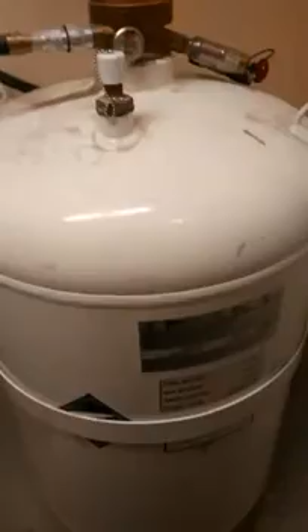FM200 fire suppression system is a clean, non-electric conducting, and environment friendly system. It is applicable for class A fire, class B fire, and class C fire, that is live electrical equipment fire. So on these three types of fire we can use this suppression system. The areas where we generally use this are the CPU room, UPS room, battery room, transformer room, data center room, and communication or telecommunication room.